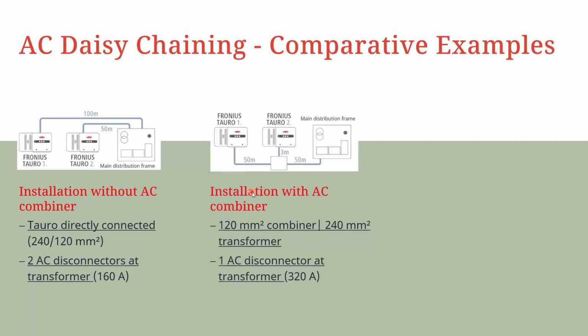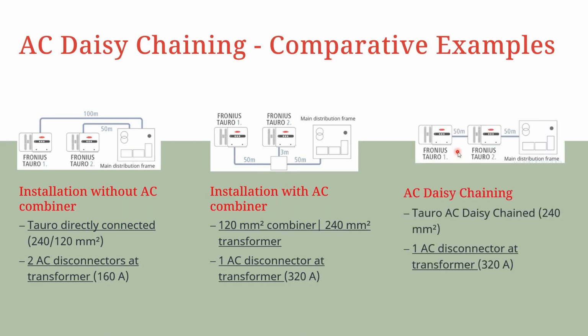Now, how about another scenario? In this case, in order to cut cable costs, we now have an AC combiner box somewhere in between. Let's say this AC combiner box helps in reducing the cable length from 150 meters to 103. Yeah, that's considerable, right? But then note that you're going to have an extra component cost of the AC combiner box. That would mean that you would have to implement an AC combiner box of 320 amps that would be enough to accommodate the current, right? So that's an extra cost. Or you can go with something as simple as this, simple and effective, using the AC daisy chaining option of the Fronius Tauro inverter. In this case, you not only have a shorter cable distance, you also eliminate the use of a combiner box. Now, how's that?